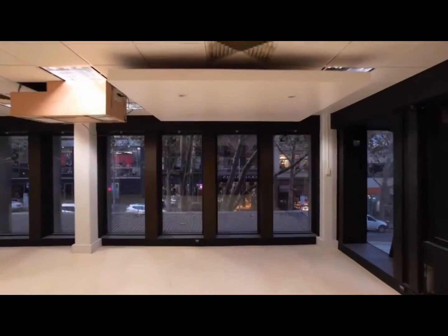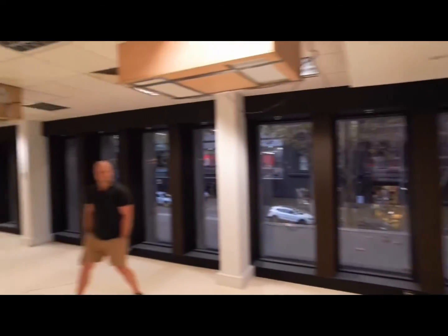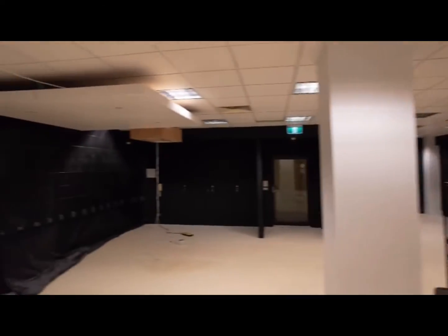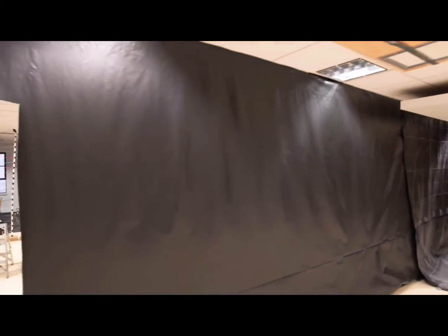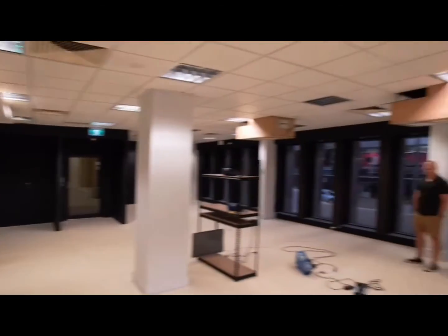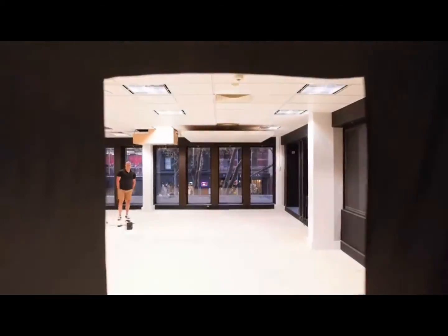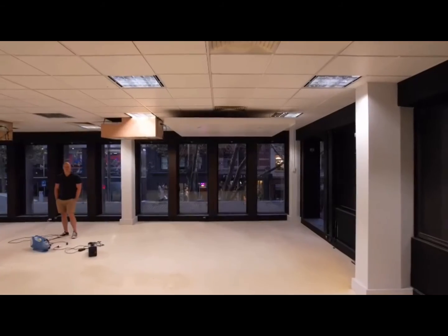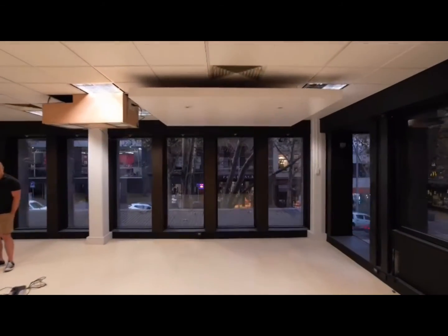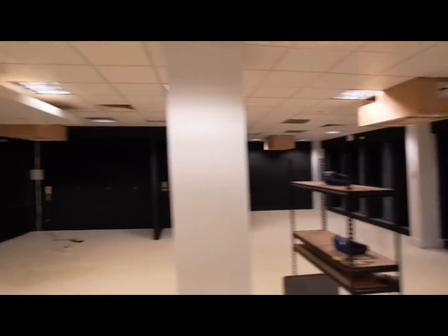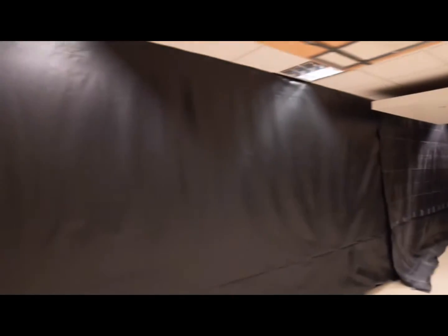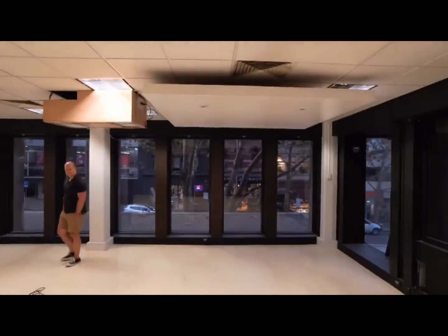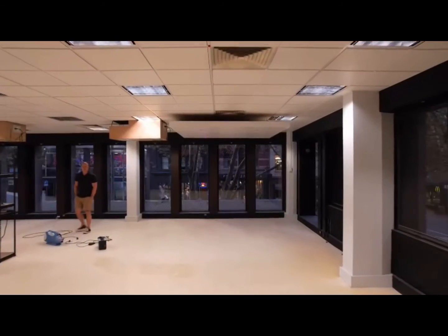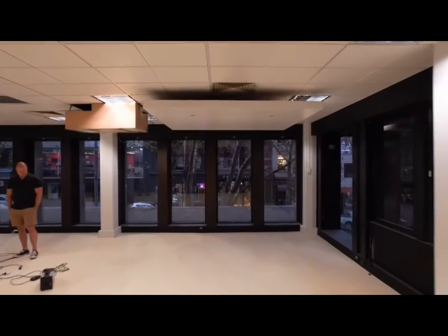The in-ceiling HEPA filter option employs devices designed and built here in Melbourne by a local company named Westaflex. These filters are similar in power use and cleaning efficiency to the air purifiers that you might see in classrooms around Victoria. However, they have one added benefit. That is, they can be tied into the building management system that a building manager or supervisor employs. This means that unlike portable HEPA filters, these are centrally tied to the building's power and tenants cannot turn them on or off, nor can they move them around. They are constantly there providing filtration to the air of the space.